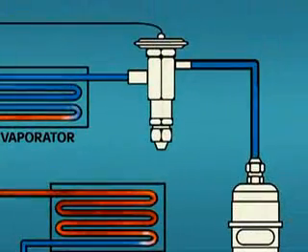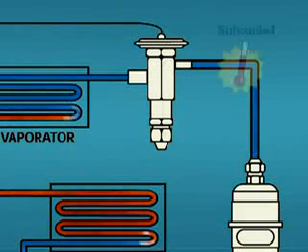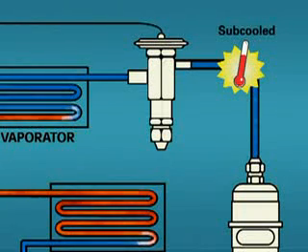With most systems, one can expect to find the refrigerant in the liquid line to have some amount of subcooling. In particular, systems employing a TEV should have subcooled refrigerant liquid entering the valve.